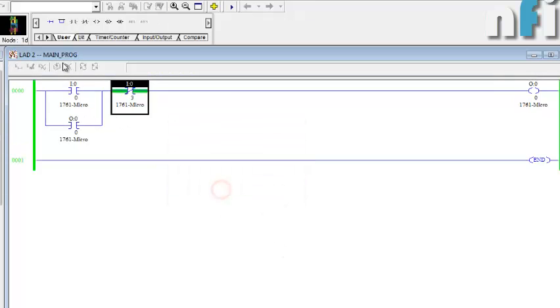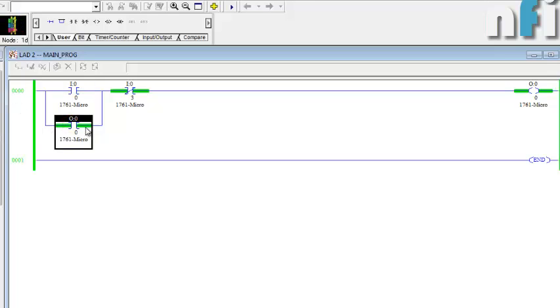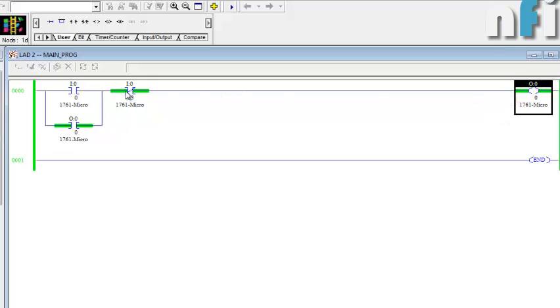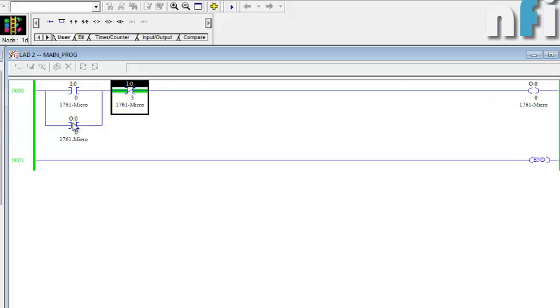Let's download and go online. Pressing I0 once and releasing — you can see it is latched because the auxiliary contact of output zero is keeping it on. Now pressing I3 will unlatch the output. The NC contact I3 breaks the latching circuit, turning the output off.